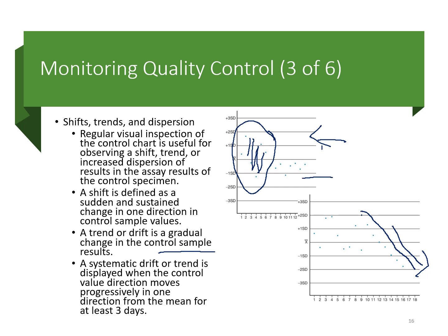Well, maybe they changed something. Maybe they saw that something was going on, so something was changed somewhere at this point to level that out. Maybe they made up new controls, or it could be a difference like the time of day that it was tested. So maybe you're finding that during the early morning hours, when all your machines are running at the same time because you're getting all those early morning samples in, the room is heating up, so it's causing some variations in room temperature, which maybe are affecting the temperature of your machine.